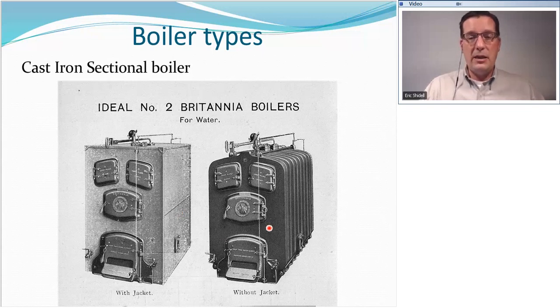One really neat thing to notice here is this was a coal-fired boiler, and the way that they would regulate the heat is with this linkage right here that would be attached to a temperature sensing element in the water, and it would open and close the burner damper to choke off the air or open it up. Pretty neat stuff. Of course, you probably aren't going to find a coal-fired boiler anymore, but you may still find this exact same boiler that has since been converted to burn natural gas instead, or one very similar to it.